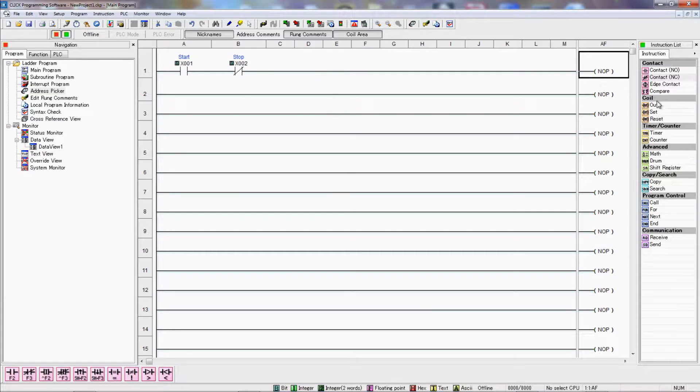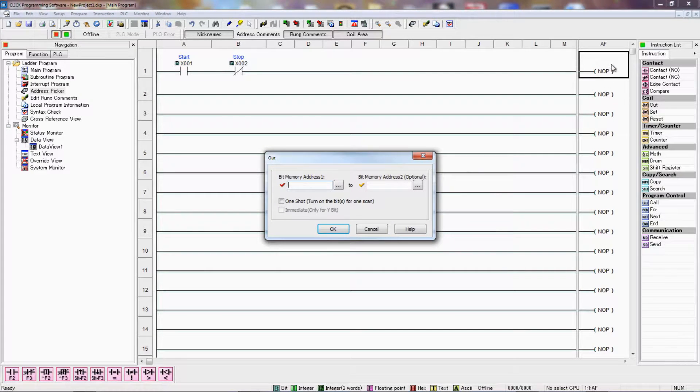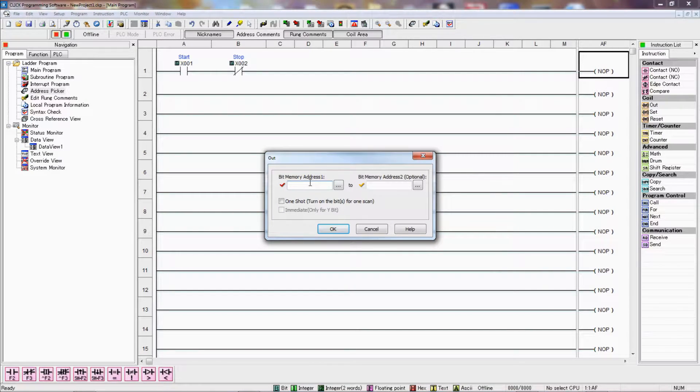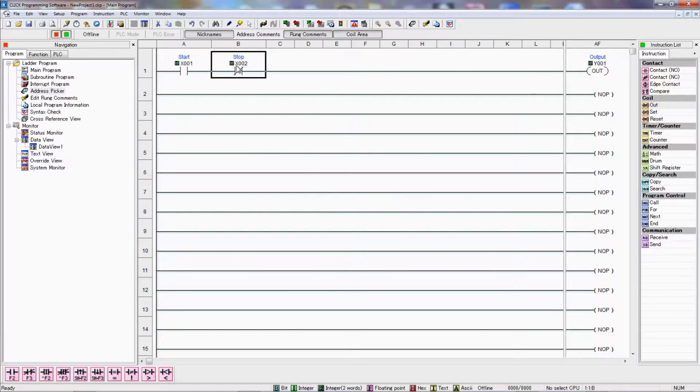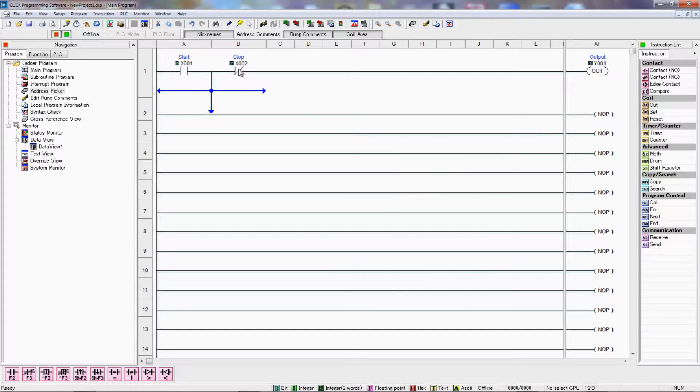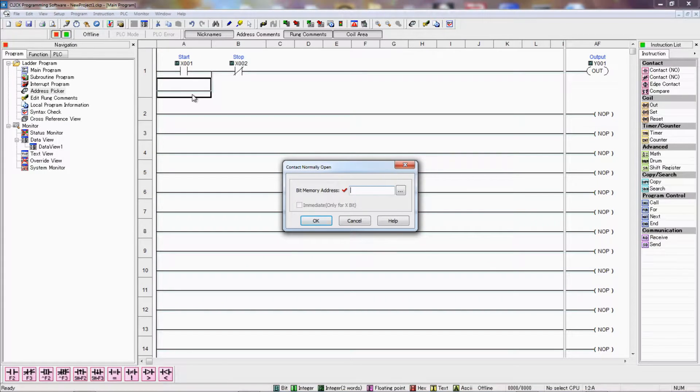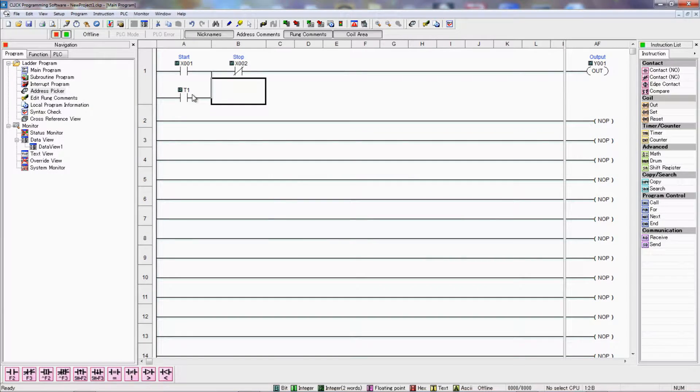And then for our output, we can drag this over, or you can also double click on it. Y1, which we know is our output. Now in order to make our seal circuit, I'm hovering over top of this, I'm holding down the control button, pressing the down arrow one time and the left arrow one time to create this branch. And I'll put another contact here, and that will be my Y1 as well.